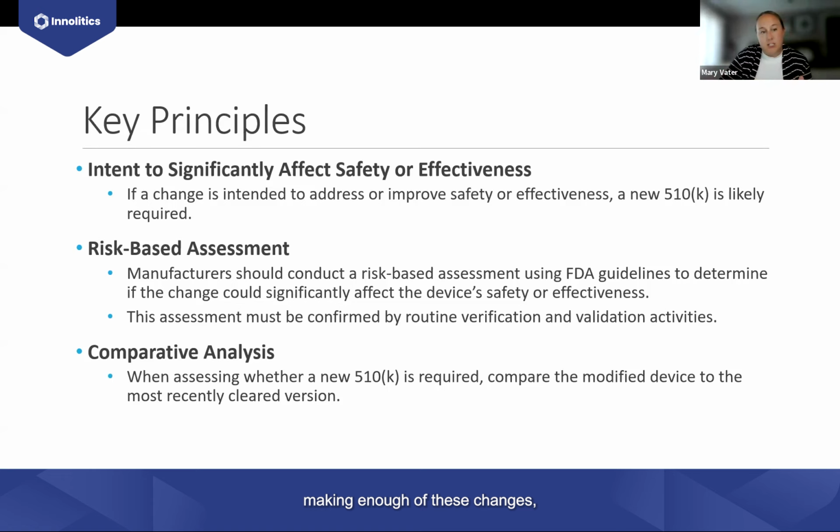cumulatively, if you're making enough of these changes, then you need to at a point consider if it's deviated far enough from the original cleared device to where it would warrant a new submission to catch up the FDA's file on the device. So oftentimes this is something companies can do proactively, but other times this is something that when the FDA comes to inspect you and they're looking through your design history file and looking at your letters to file and your change notes, they might say, okay, you've made a lot of letters to file. You're kind of getting pretty far. We would recommend you do a catch-up 510K. So not necessarily the core focus of these guidances, but just something to be aware of if you are planning on making a lot of small changes to your device.